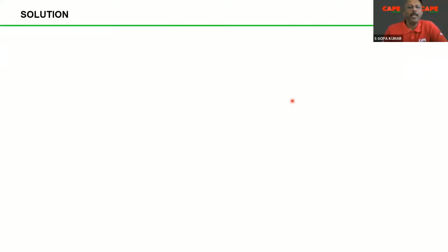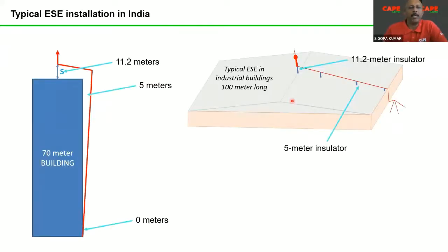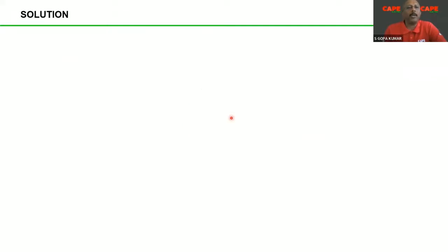So basically, the separation distance calculations are very much included in the standard. This is mainly applicable for large buildings. For smaller buildings, the distances are quite small, because of the length of the equipotential, the length I am showing with the cursor, 70 meters. In a normal building, probably 7 meters. Then the calculation changes. So this is actually a challenge. Whenever you do lightning protection, please always keep in mind that lightning protection is not only about air terminal, down conductor, earthing and SPD. It is also about the separation distances, if the technique implemented is an exposed, isolated lightning protection system. So now, what is the solution?